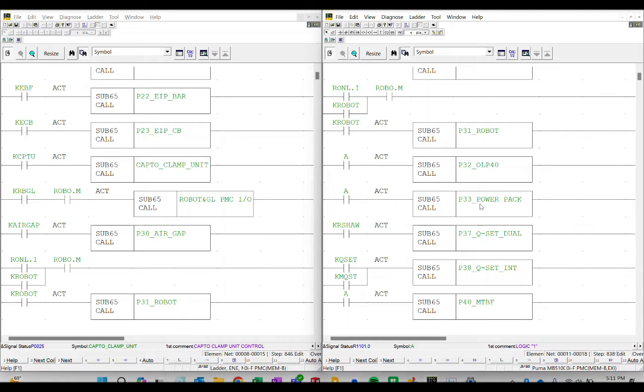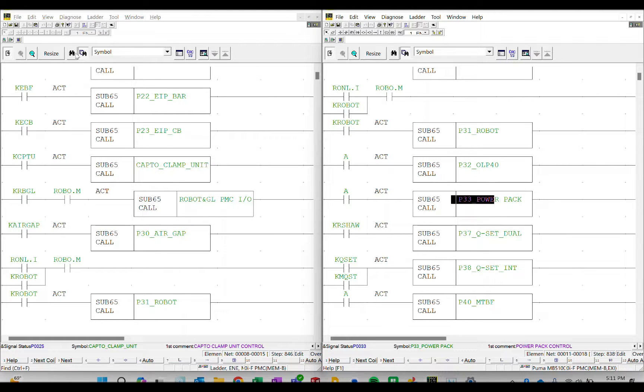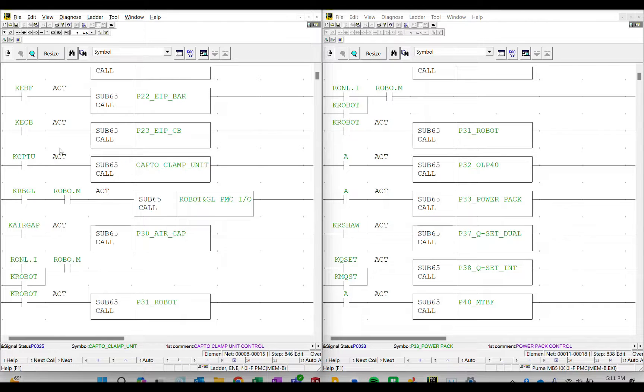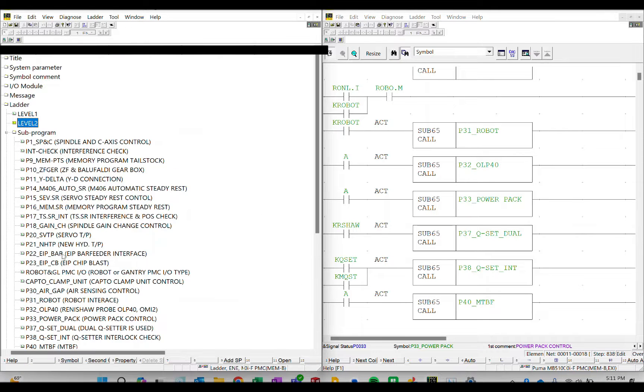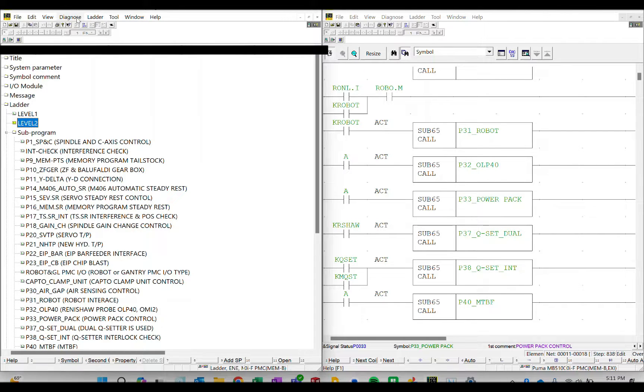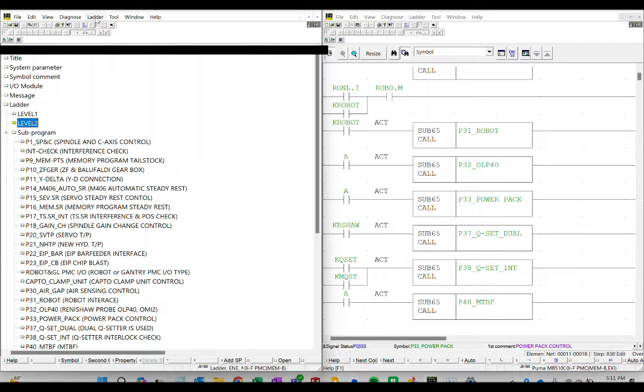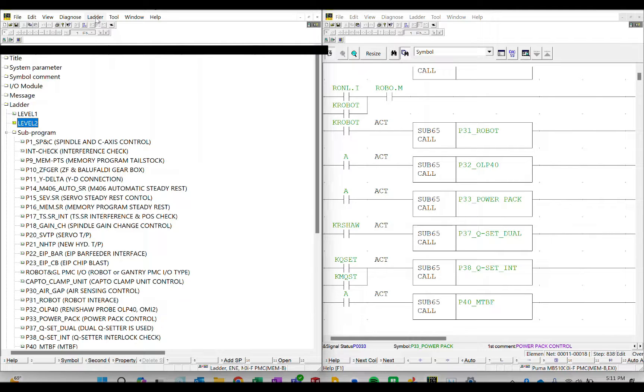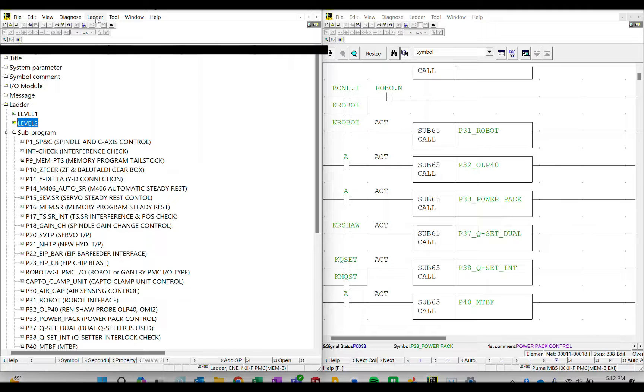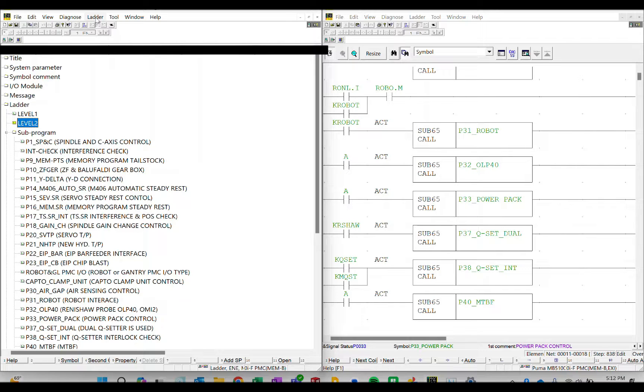But then I got thinking about a new problem that I was pretty sure was going to happen since the old ladder had some of the outputs that we cared about. We have to go find the duplicates. For example, if we're trying to turn on a valve and we're commandeering some other output, that other output is written somewhere else. If the program is running through the ladder sort of top to bottom and it meets our line of code that says turn the output on, and then it cruises down 250 lines later it finds that same output says that it should be off, that's the problem that we're trying to solve.